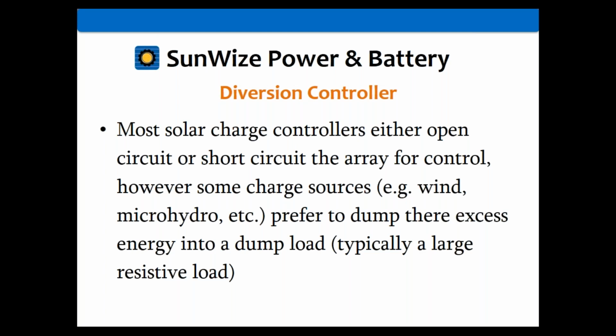Examples are wind and micro hydro systems. They prefer to dump the excess energy because they want the device to keep spinning, whether it's a wind turbine or a micro hydro turbine. So when the batteries are full, but you don't want to overcharge them, you divert that energy instead, which is how you get the name diversion controller, to a load dump, typically a resistor, though it could be something else. Usually that energy is just dumped as heat into something. That's what a diversion controller does.